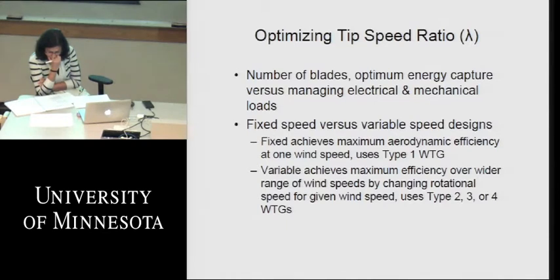A couple things about the fixed speed or constant speed versus the variable speed designs. Again, a Type 1 is a fixed speed design, or a constant speed design, and it achieves its aerodynamic efficiency at 1 set speed. And when the wind changes, it becomes less efficient, but we have no way to control that. The Type 2 and 3 and 4 will actually pitch their blades, so we can control that. So the variable speed type generators or wind turbines achieve a greater efficiency over a wider range of speeds, because we can actually coordinate the whole operation of the wind turbine as the wind changes. Next slide.